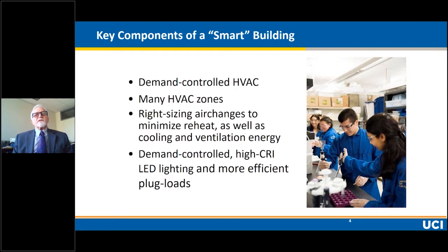It's controlled by sensors. So, for example, in a lecture hall, we're sensing not just whether there are people in there, we're sensing what the CO2 level is in the return airstream. In laboratories, we're sensing more sophisticated things like particulates down to a very small level. We're sensing VOCs, volatile organic compounds, which is very important in laboratories for safety. And so then we're right-sizing air changes based upon real-time sensors.